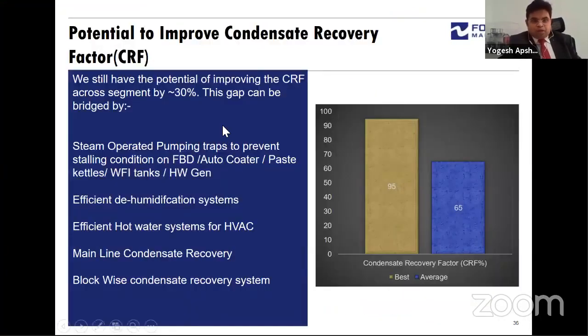Condensate recovery is a major aspect in formulation plants. But the typical challenge in formulation plants is that the equipment is quite scattered. If you leave aside the clean room, which has a pure steam generator or MCDP, and the WFI storage tanks, purified water storage tanks and the SIP systems, only these sets of equipment are in the same place. Otherwise, small equipment like SIP systems, FBDs or auto coaters are quite scattered as per demand and the type of factory, whether oral solid dosage or liquid dosage.